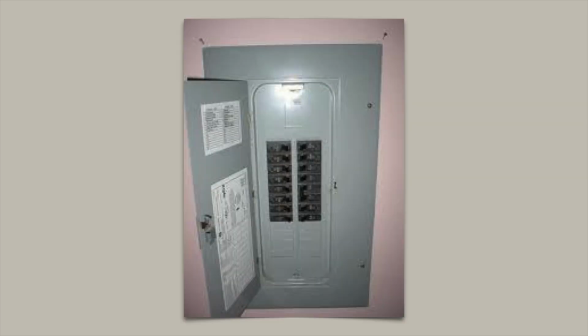A residential house should have a residential panel. All residential panels, designed for the residential market, have a main breaker. If you see a main panel without a main breaker, write this up as a safety defect. There are some home inspectors that say the main panel is safe as long as 7 swipes of your hand will turn off all of the branch circuits. If this was so, why have main breakers? The fact is that panels that don't have a main breaker are designed for and used in commercial applications as distribution boxes. They are not designed for use as a residential main panel. They may be electrically functional, but their use in a home is not appropriate.